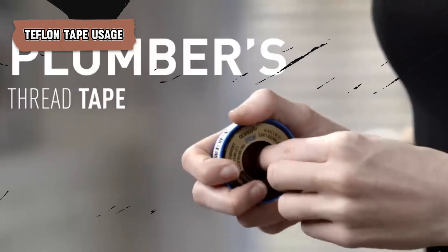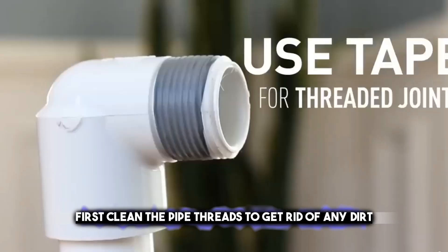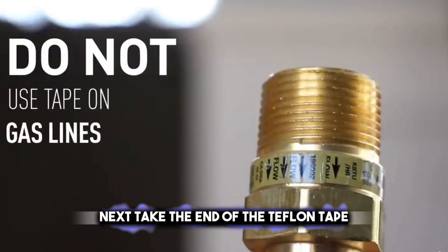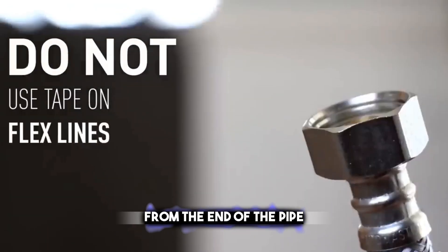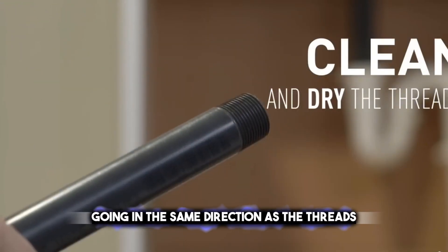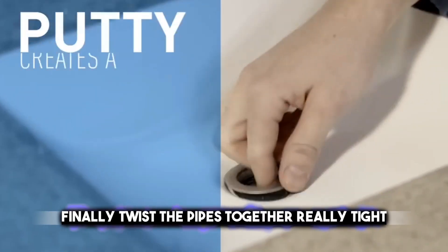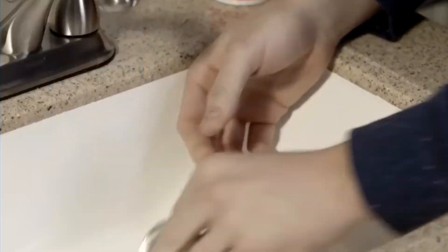Teflon tape is really important for making sure pipes are screwed together without any leaks. First, clean the pipe threads to get rid of any dirt. Next, take the end of the Teflon tape and place it on the second thread from the end of the pipe. Wrap the tape tightly around the threads, going in the same direction as the threads, about two to three times. Be sure the tape covers all the threads but doesn't go over the end of the pipe. After wrapping, press the tape down into the thread so it sticks. Finally, twist the pipes together really tight. This way, you'll have a tight and leak-free connection that keeps your pipes in good shape.